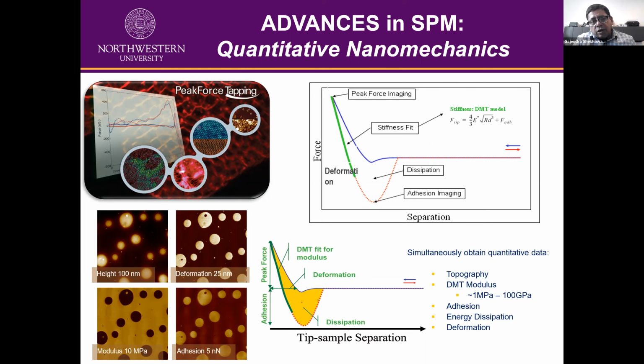Okay, so this is very popular. Here we modulate the probe at 1 or 2 kilohertz, which is well below the resonant frequency of the cantilevers. And the advantage of this technique is you can look at the force separation graph. You can see here we can quantify a lot of things. You can do the adhesion measurements. You can do the energy dissipation, which is the area under this loop here, if you have adhesion. And then you can also do the deformation, how much the sample has been deformed.